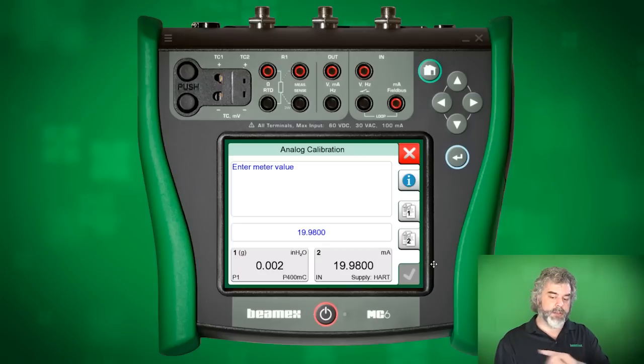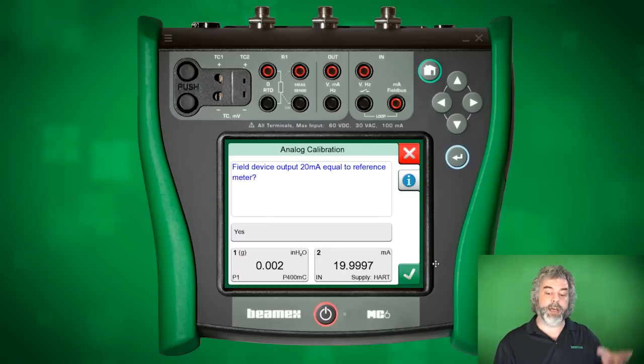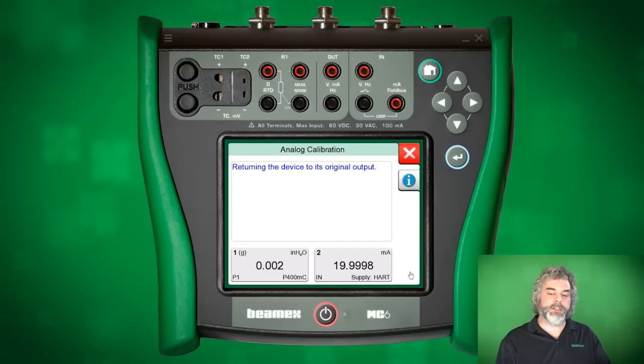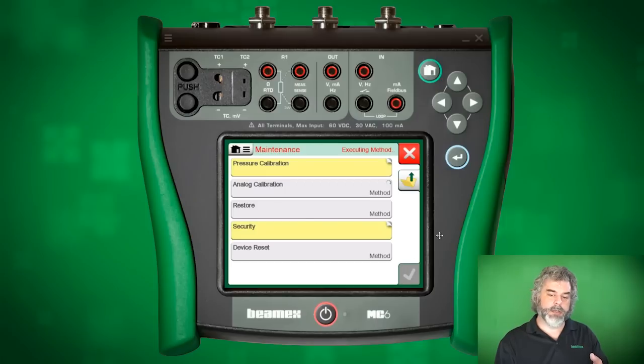So let me hit check. And then watch the bottom right. Okay, now it's fixing itself. Let me hit check. So that one's like 3 microamps off, but that's fine. Most meters can't even measure a microamp, so this is okay. Now we're just waiting for the red lettering to go away.